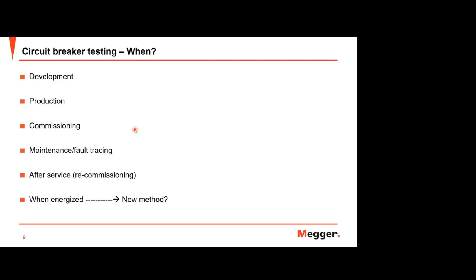And we do circuit breaker testing in many conditions. Of course, from development, this is mostly done by the circuit breaker manufacturer before they develop some product. They need to test to make sure all specs are as expected. And production, after they produce some circuit breaker, they need to test to make sure the spec is in range. And commissioning, this is mostly on the customer side or the user side. After they receive the circuit breaker, they need to test that it has the spec the manufacturer mentioned.